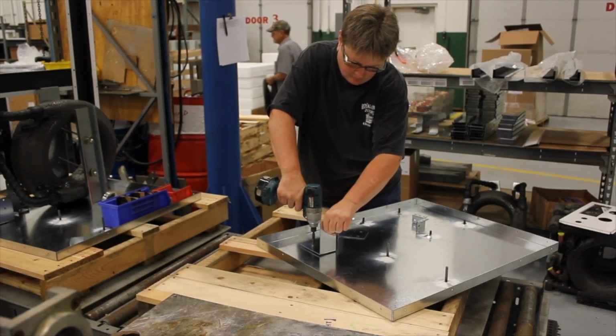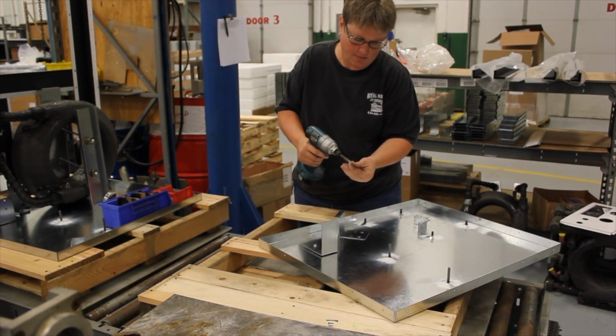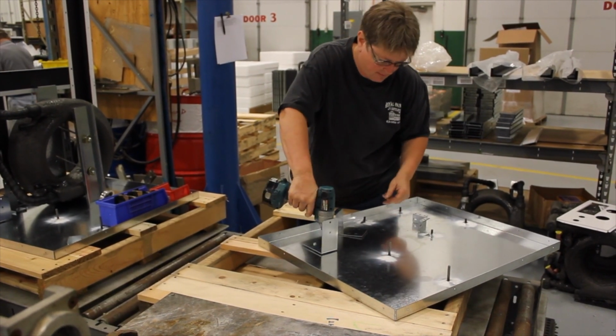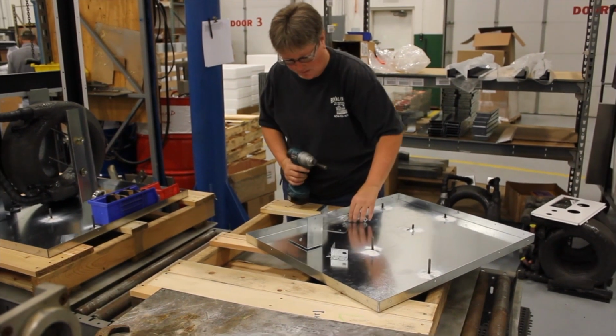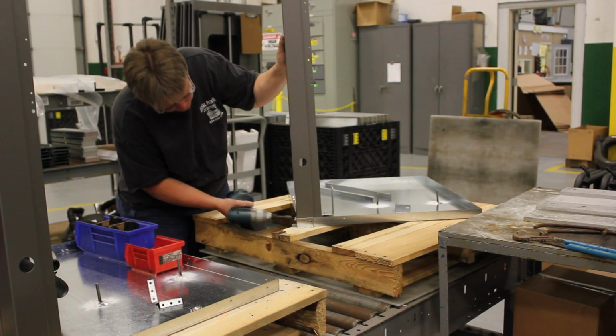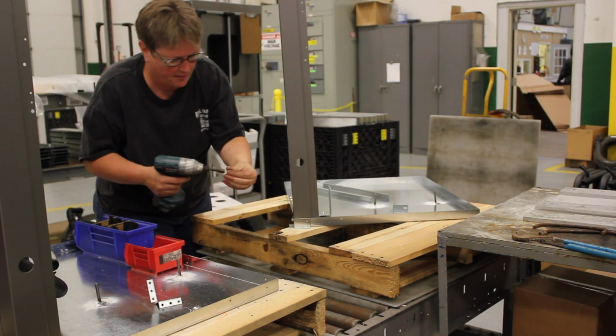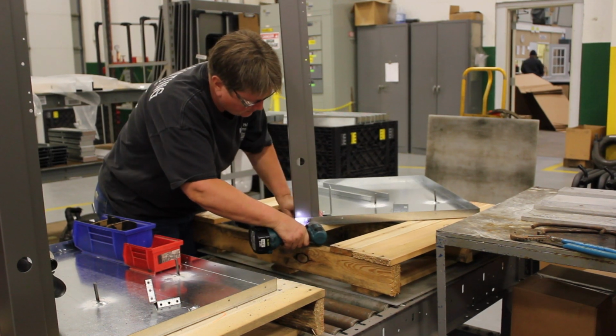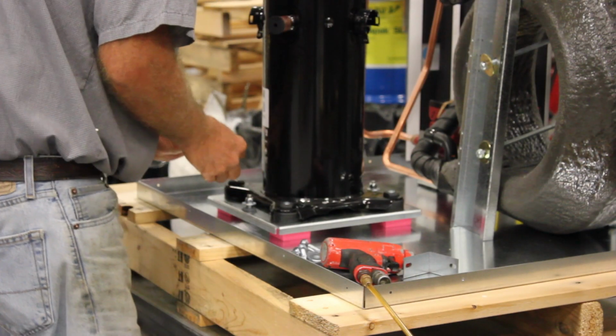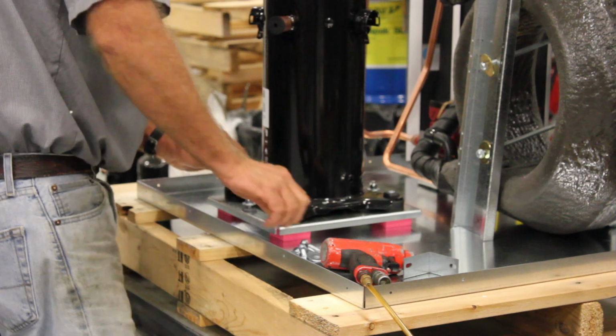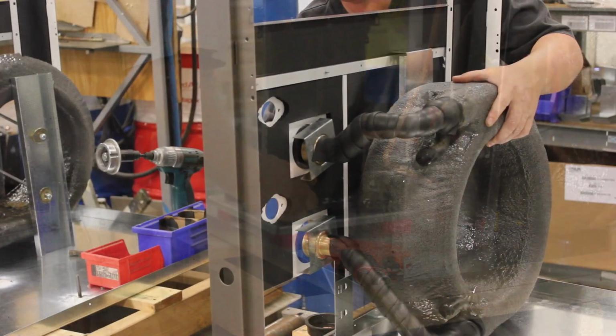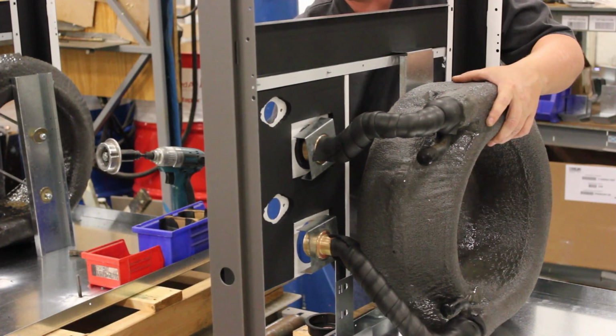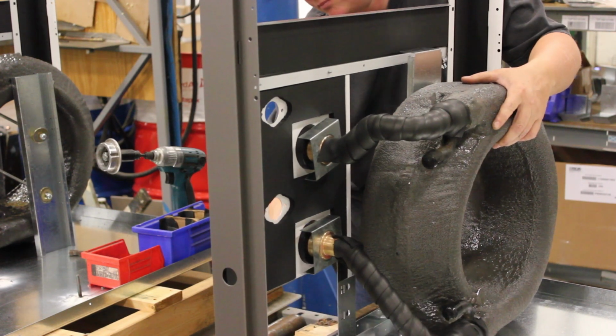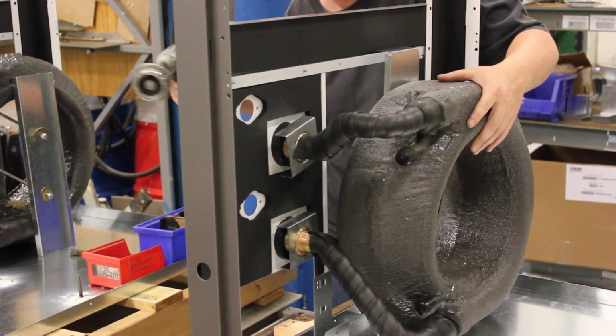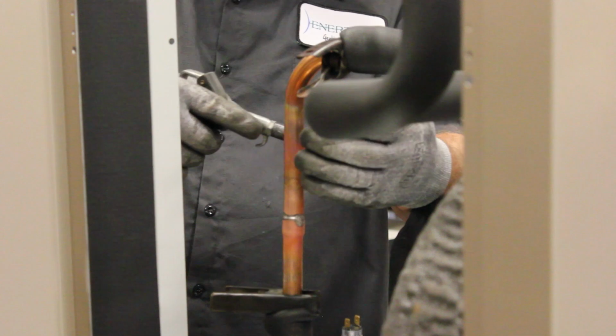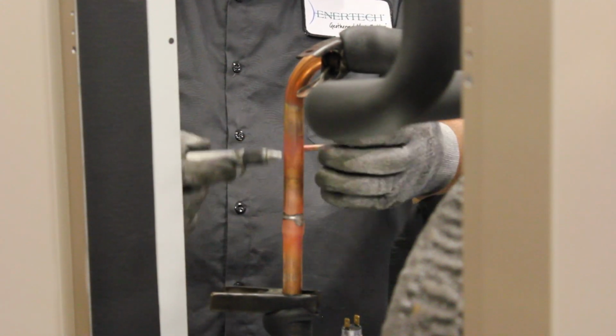Now we are ready to begin hand constructing our world-class geothermal heat pumps on the assembly line. Each geothermal system is built from the ground up, starting with a pallet underneath to protect it from damage. Once the base pan and cabinet legs are assembled, we are ready to install the compressor and the coaxial heat exchanger. Enertech uses an exclusive proprietary process to foam coat our coaxes to protect against moisture and improve unit performance and reliability. The unit continues down the line where various subassemblies are installed.